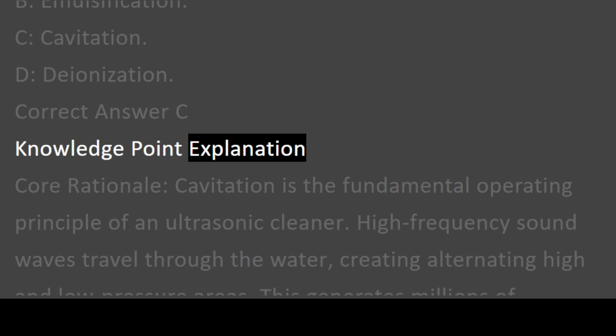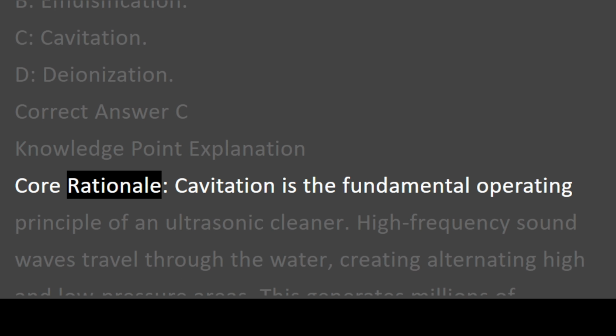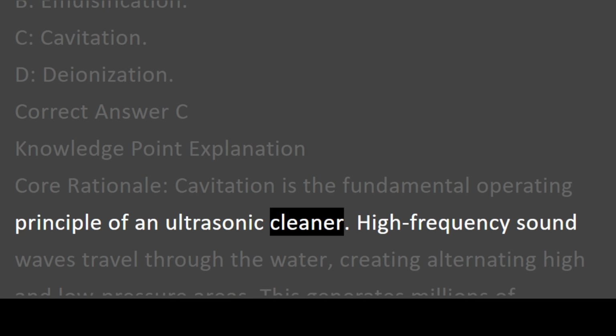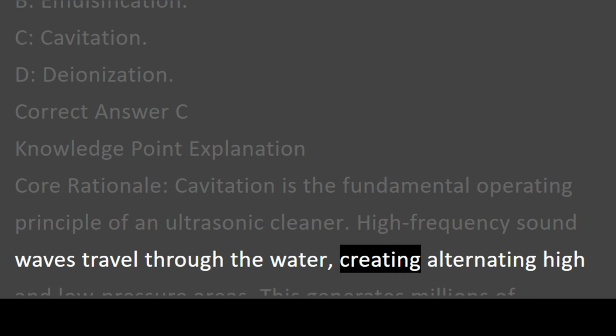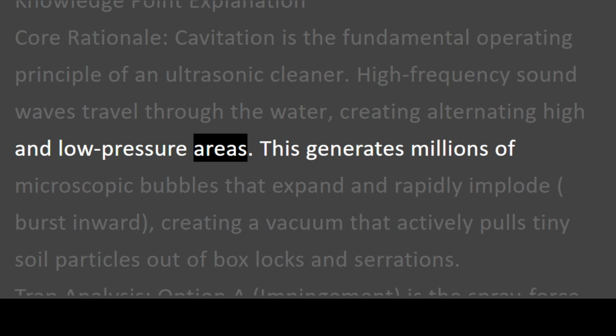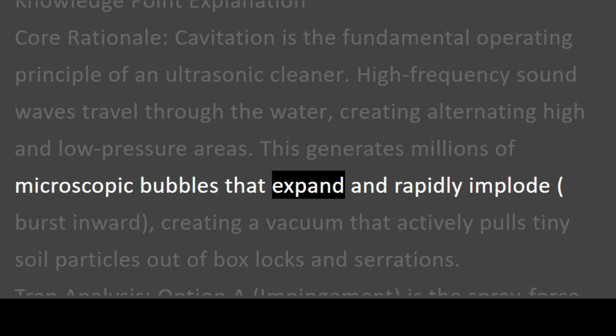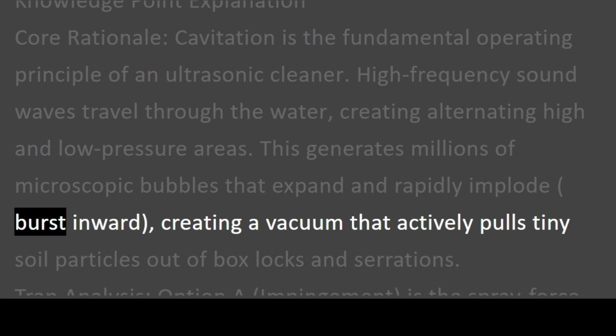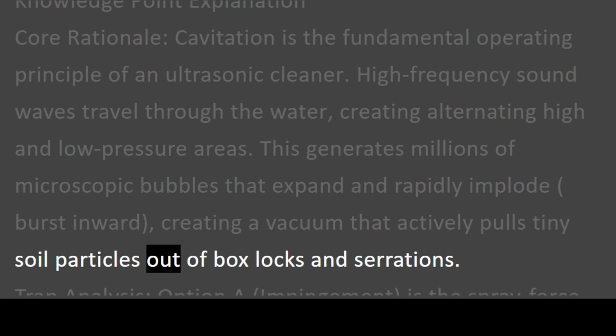Knowledge point explanation. Core rationale. Cavitation is the fundamental operating principle of an ultrasonic cleaner. High-frequency sound waves travel through the water, creating alternating high and low pressure areas. This generates millions of microscopic bubbles that expand and rapidly implode, burst inward, creating a vacuum that actively pulls tiny soil particles out of box locks and serrations.